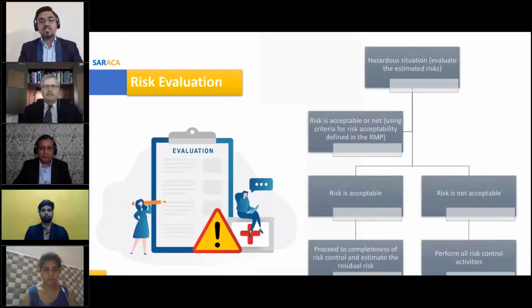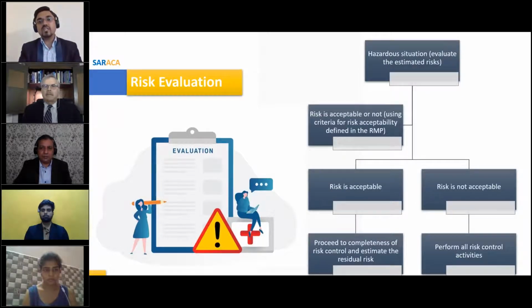So risk evaluation. How do you evaluate a risk? From a hazardous situation you can identify the risks, but evaluating the risks is very critical. So when a hazardous situation arises, you can evaluate the estimated risks. You can get this hazardous situation from your PMS data, from the complaints, from the customer feedback, and from the PMCF as well. So you can get hazardous situations during these processes.